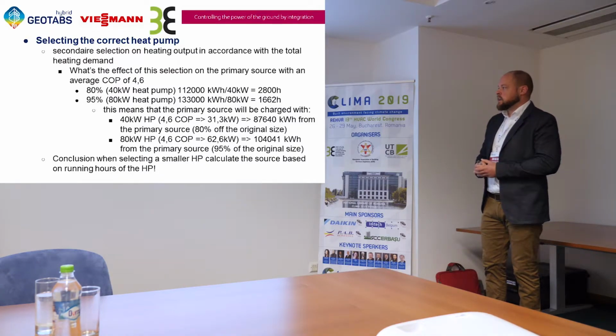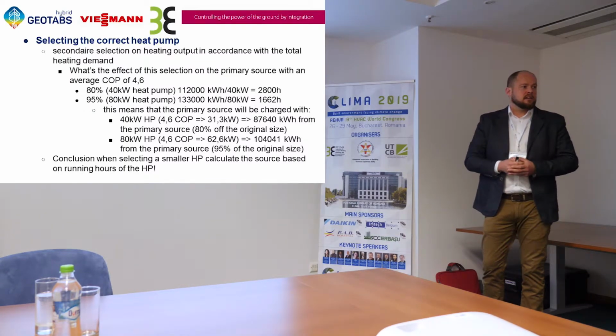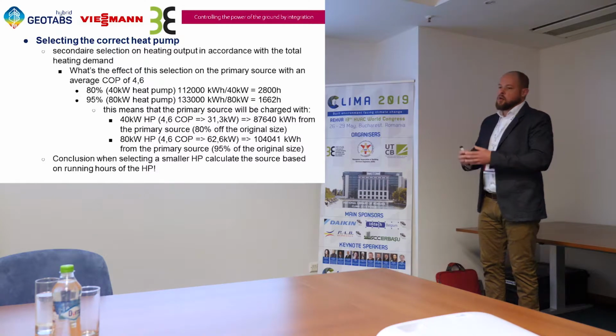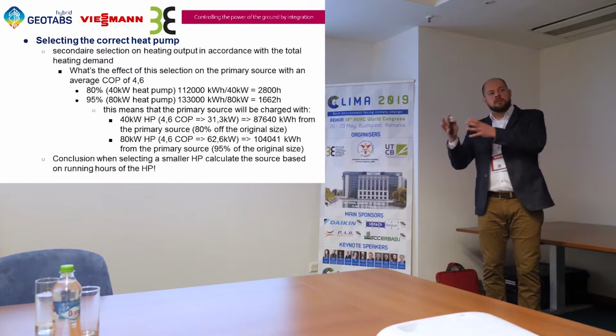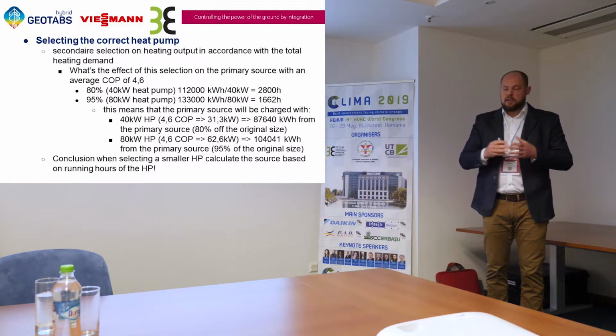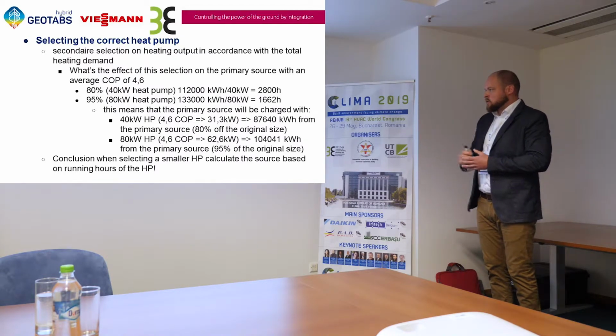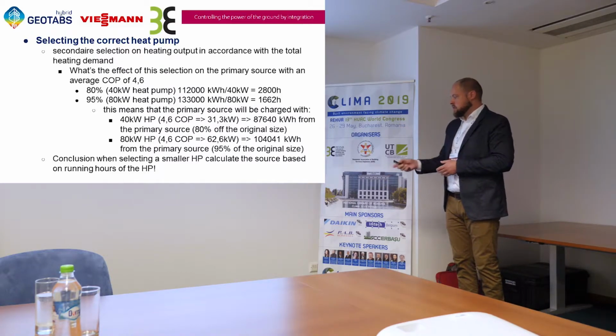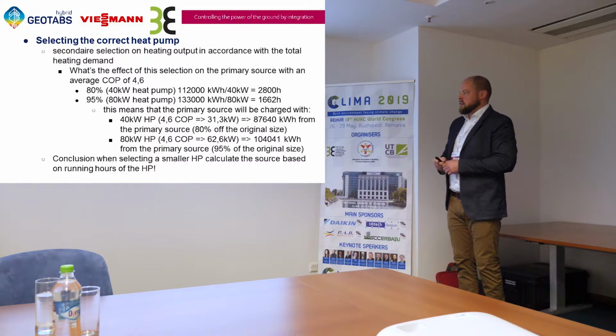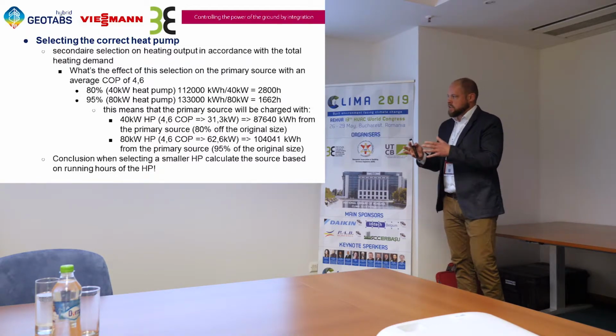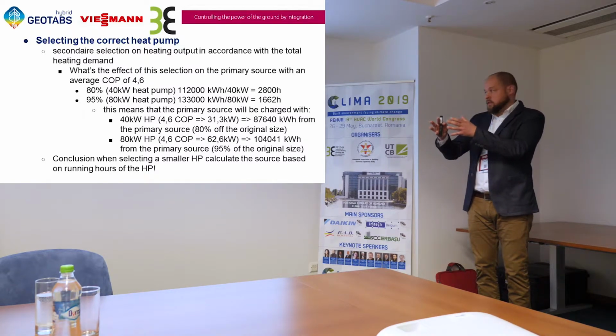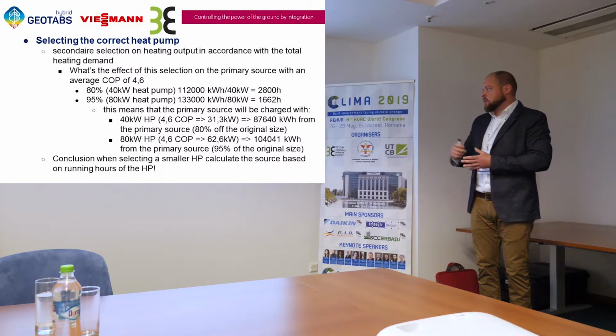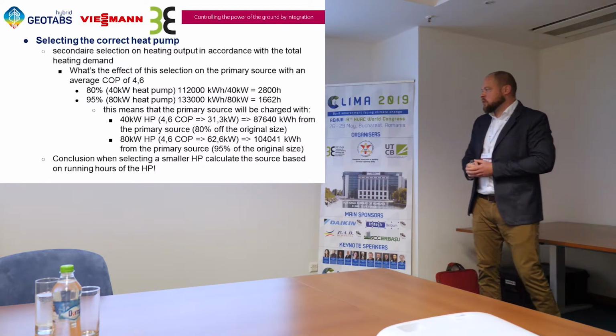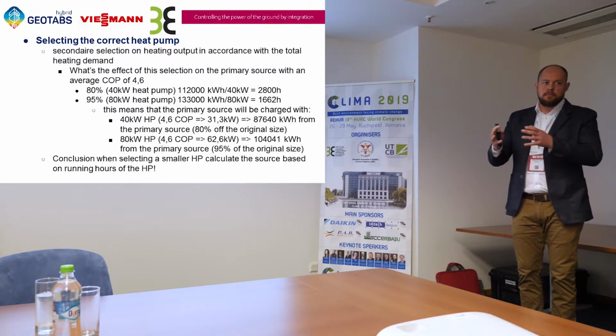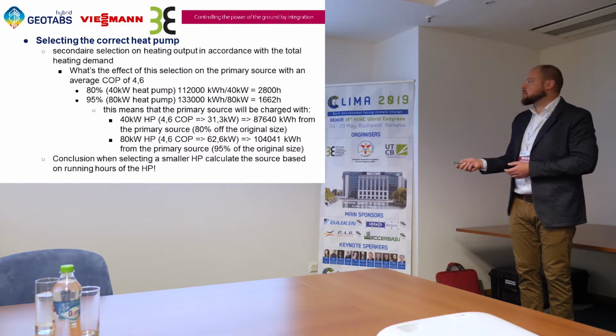That's actually a lot. That means that it's actually 80% of the original sizing. So it's very important to not make the mistake, oh, I have a heat pump, it's only 40% of the total heat load. I will make the borefield only 40%. So then we will have a problem during the heating season. You can also see that at 80 kilowatt heat pump, also with a COP of 4.6, we will almost be at 95% of the original size of the source. So that's very important to know that when you select a smaller heat pump, the running hours will be much more than normal with a 100% selection, and that we will use the source in comparison here 80 and 95% of the original size. So when selecting a smaller heat pump, calculate the source based on the running hours and not on the power output from the heat pump. That's a very important conclusion.